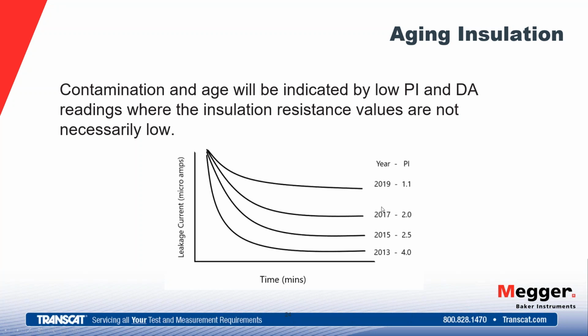So here we see, over time, the progression of contamination and/or age. If it's clean and dry through this period, then this is an indication of age. As we take data points, here every 2 years, our PI values are steadily getting less due to contamination or age of that insulation. Contamination is what we first suspect. If that motor is clean and dry, then we suspect age of the insulation.